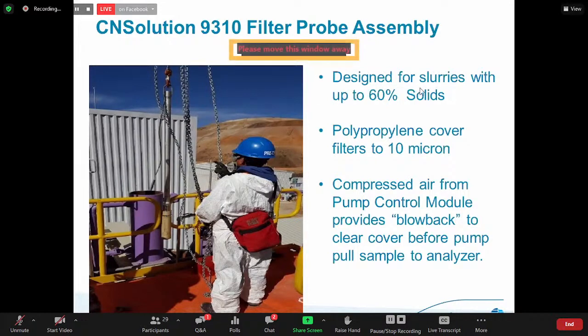So this was designed for slurries with up to 60% solids. It's a polypropylene cover that filters to 10 micron. And as I showed in the previous slide, compressed air from the pump control module provides a blowback. It clears the cover before the sample pulls in, and then the pump turns on and pulls the sample into the instrument. So this is raised and lowered down into some point in the slurry tank to pull the sample into the instrument.